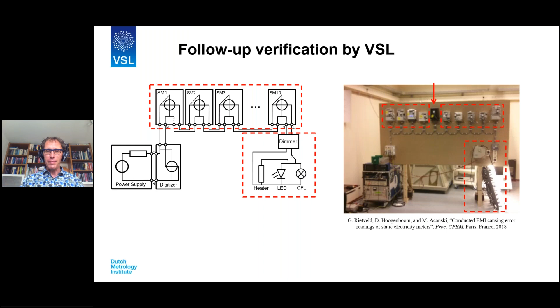But instead of using an electromechanical meter as a reference, we used our own reference system with a calibrated broadband voltage divider, current shunt, and high precision digitizers. A computer was used to read out the digitizers and optical pulse signals from the meters under test.